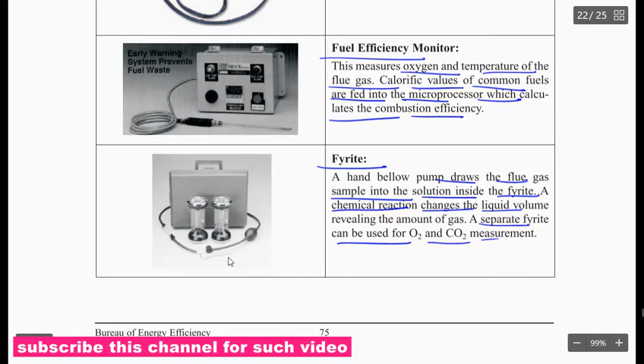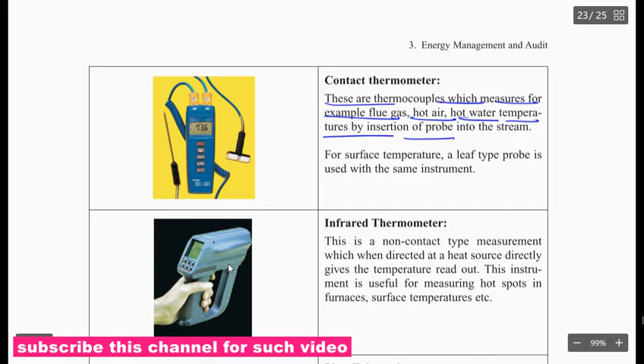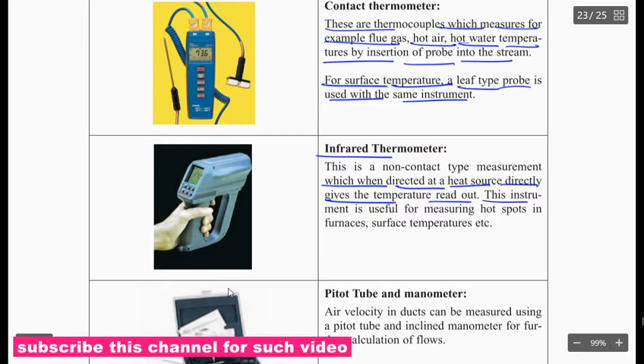Contact thermometer. These are thermocouples which measure, for example, flue gases, hot air, and hot water temperature by inserting a probe into the stream. And for surface temperature, a leaf type probe is used with the same instrument. Infrared thermometer. This is a non-contact type of measurement which, when directed at a heat source, directly gives the temperature readout, and the instrument is useful for measuring hot spots in the furnace and surface temperature.